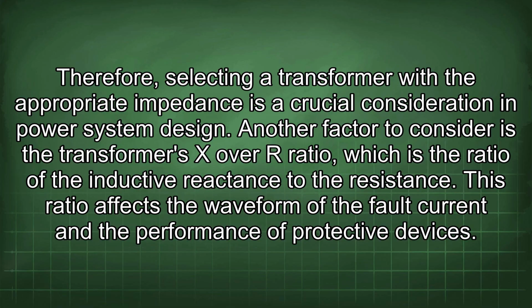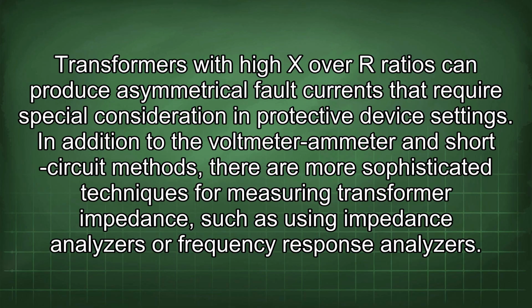Another factor to consider is the transformer's X/R ratio, which is the ratio of the inductive reactance to the resistance. This ratio affects the waveform of the fault current and the performance of protective devices. Transformers with high X/R ratios can produce asymmetrical fault currents that require special consideration in protective device settings.